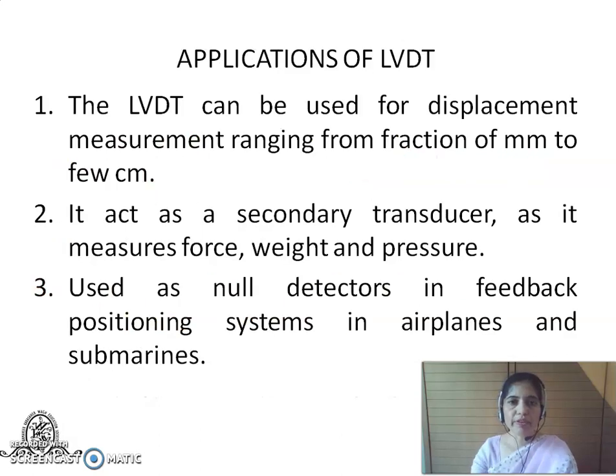Some of the applications of LVDT, as already stated, is that it is used for measuring displacement, typically in the range of a fraction of a millimeter to a few centimeters. It can also act as a secondary transducer, that is, if one wants to measure force, weight, or pressure, then these quantities can be converted into proportional displacements, and these displacements can be captured by the movable core, thereby resulting in an output voltage at the secondary. LVDTs are popularly used as null detectors in feedback positioning systems in airplanes as well as submarines.